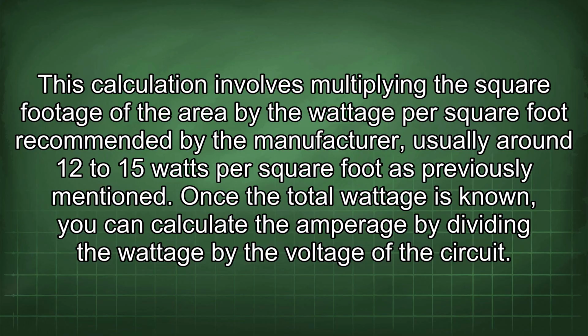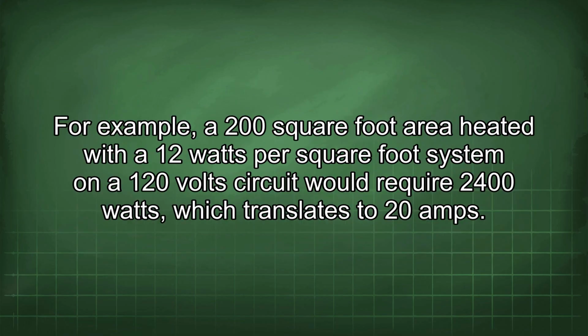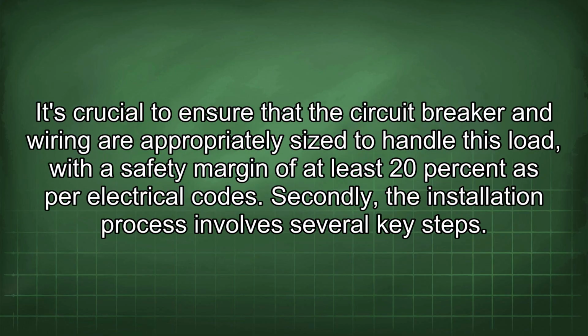Once the total wattage is known, you can calculate the amperage by dividing the wattage by the voltage of the circuit. For example, a 200 square foot area heated with a 12 watts per square foot system on a 120 volt circuit would require 2400 watts, which translates to 20 amps. It's crucial to ensure that the circuit breaker and wiring are appropriately sized to handle this load, with a safety margin of at least 20% as per electrical codes.